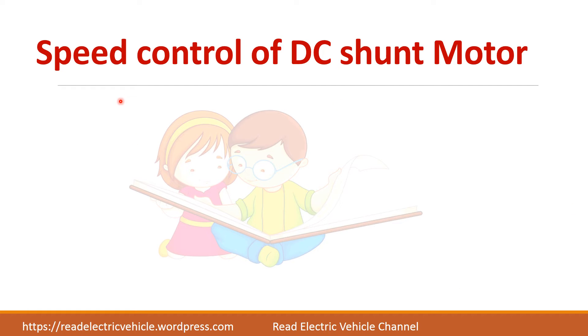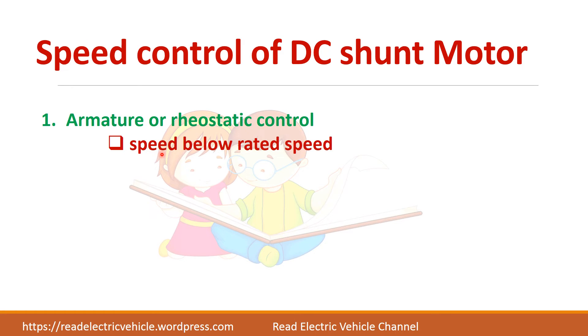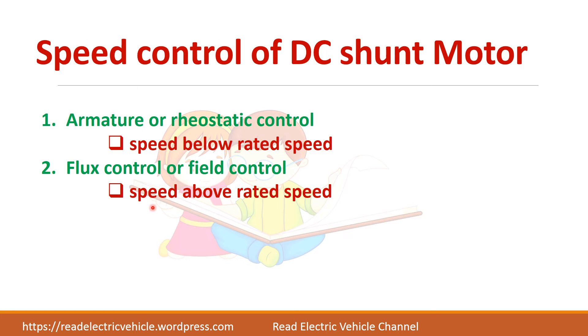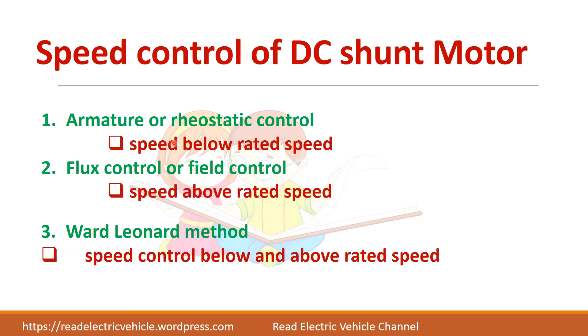So far we have seen speed control of DC motors. There are basically two types: armature or rheostatic control, which is used to control the speed below the rated speed; and flux control, where we are able to achieve speed control above rated speed. But if you want both — control below rated speed as well as above rated speed — there is one more technique called the Ward-Leonard method, where you are able to achieve both below and above rated speed control.